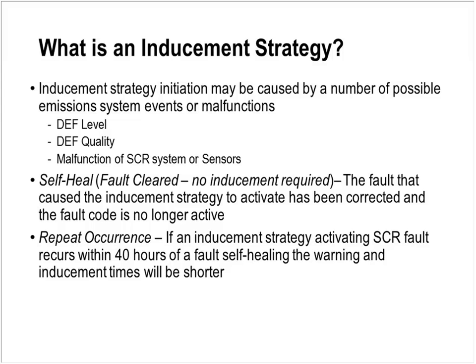So it's important to understand, with your life-critical installations, that on our Tier 4 certified unit, an unresolved fault with the after-treatment or the SCR system will currently result in the unit shutting down after a 4-hour period. Now, there has been widespread objection to that from the industry as a whole. Emergency systems are there for just that. They're there for emergencies, and the last thing we need is unresolved issues.